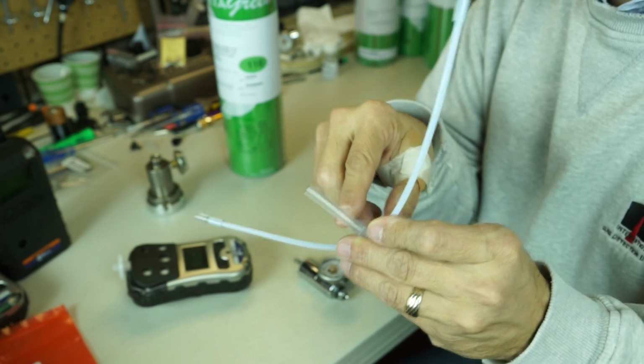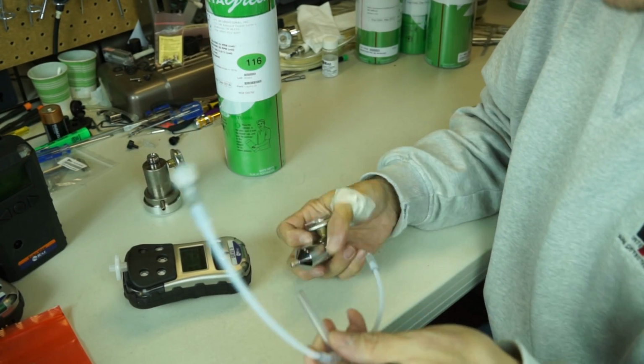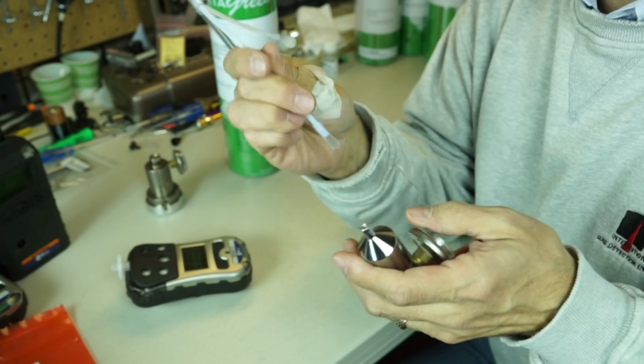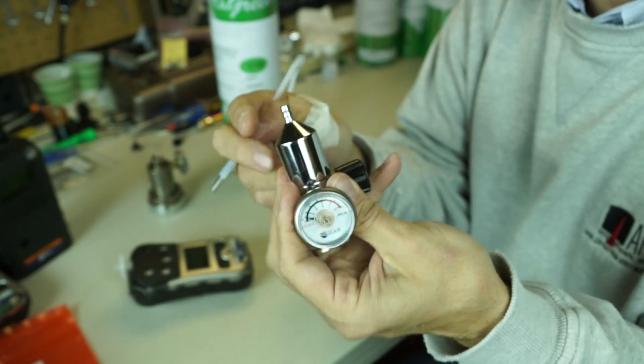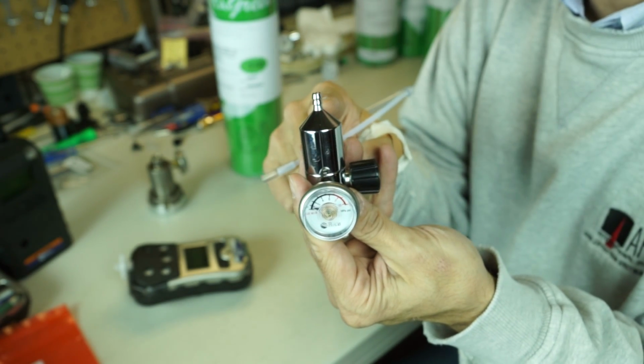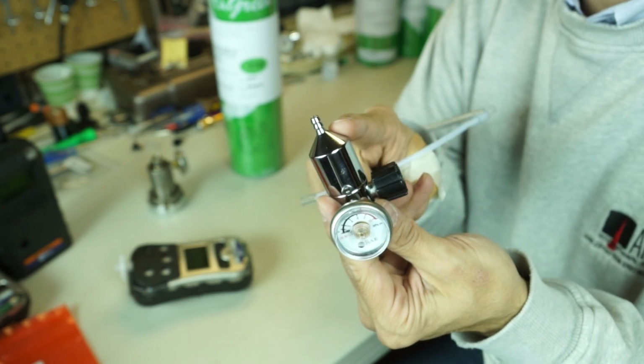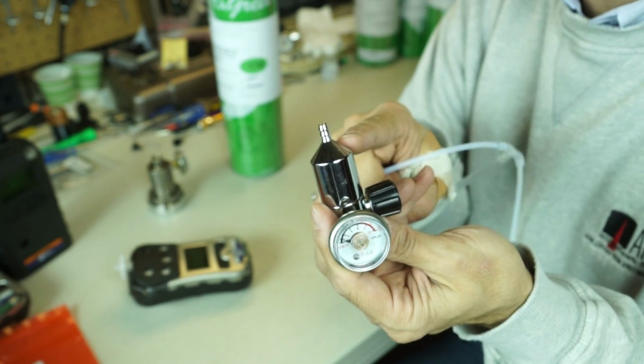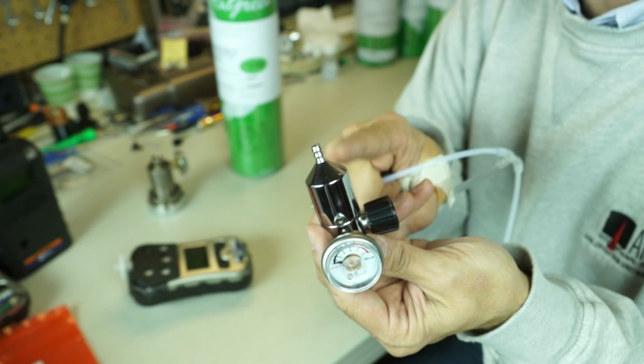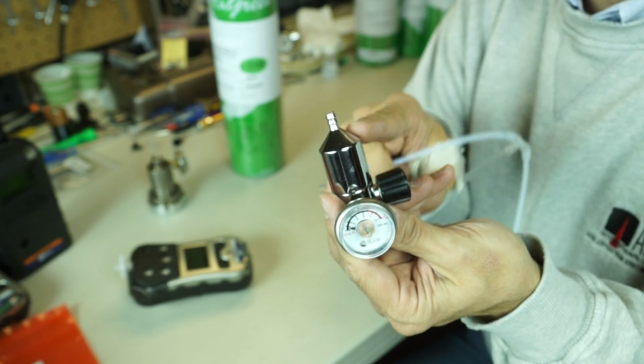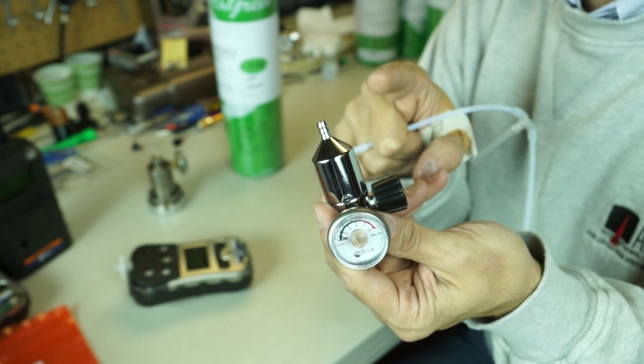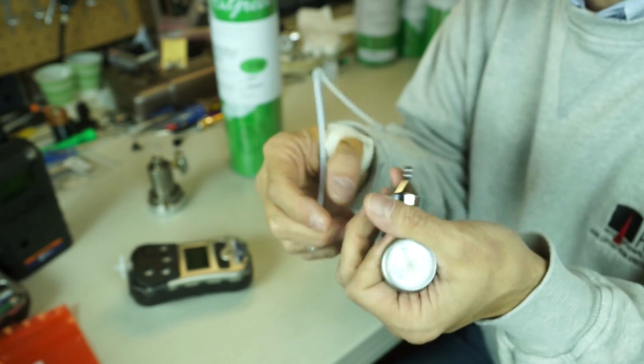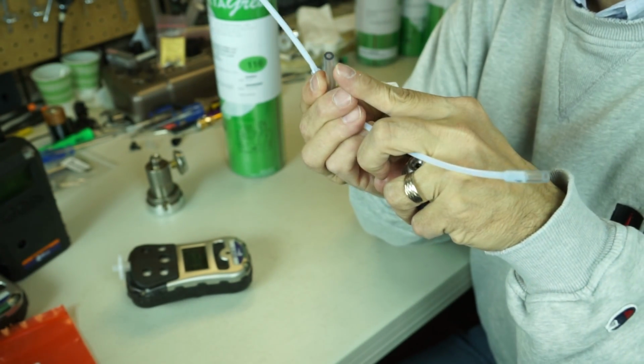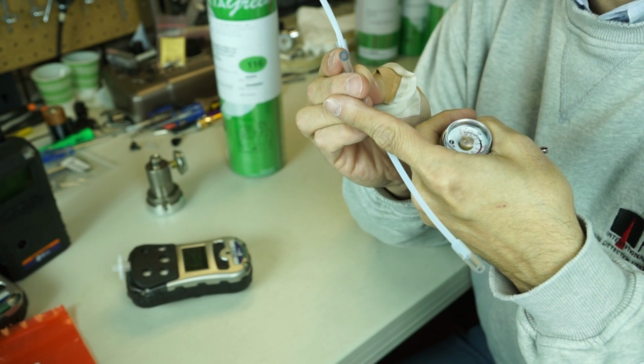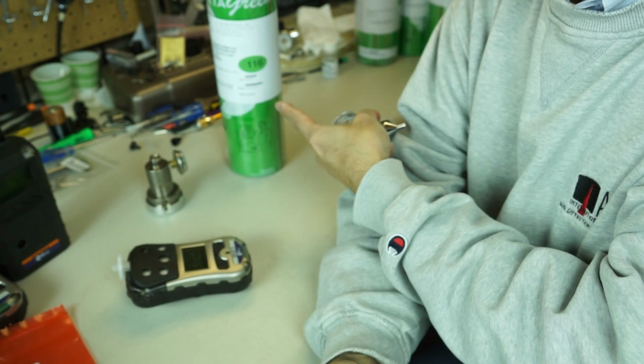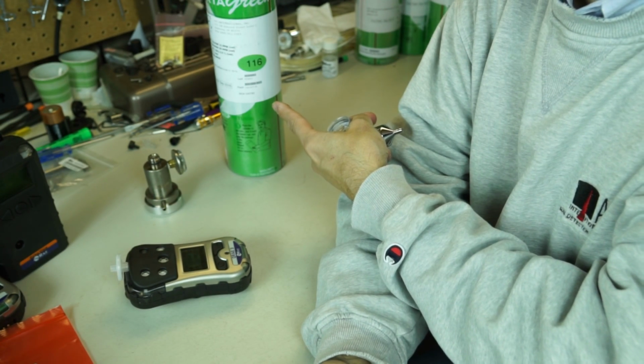So what I'm going to do here is go ahead and connect the calibration T to the regulator. This is a fixed flow regulator from Rae Systems. And the key thing here is you have to make sure you use a regulator that has a flow that's greater than the draw of your instrument. If this regulator doesn't have a flow greater than the instrument's draw, then the third leg of the T is going to act as a dilution probe, and that will reduce the gas concentration that we have in the cylinder.